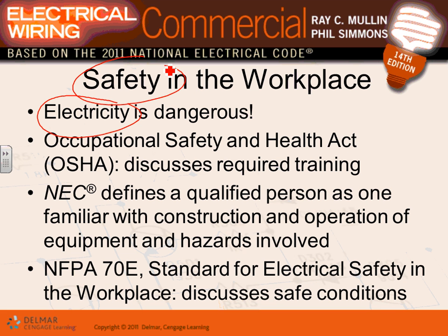So be aware. Stay away if the electricians are working on this panel and you're the designer there. Make sure you keep at least 9 to 10 feet distance from the energized object, the panel. If there's an arc flash, arc blast, the electrician should be in PPE, have the proper gear on them. You are not authorized, licensed, or qualified to work on energized objects. So you shouldn't be in the whole area. Be aware of that one.